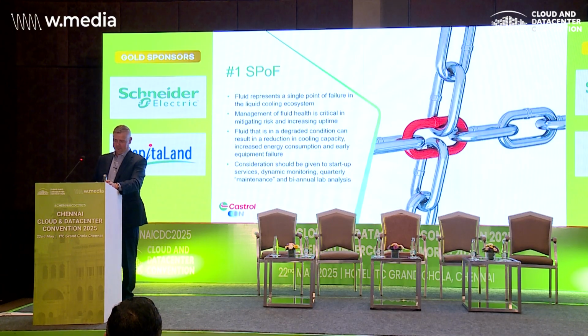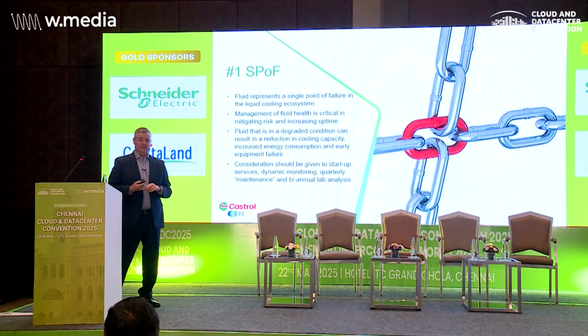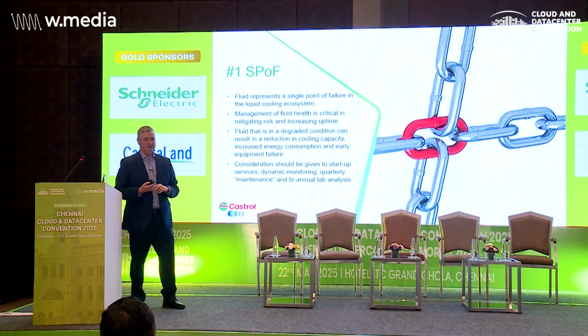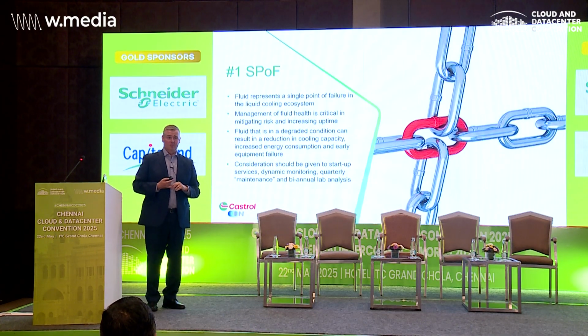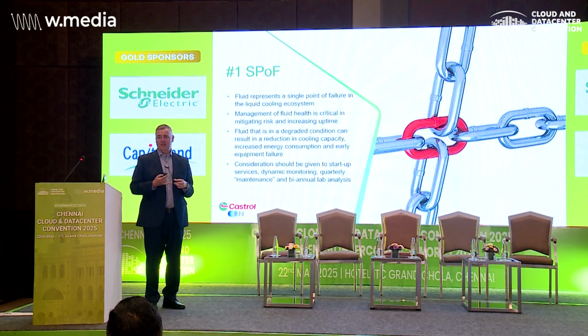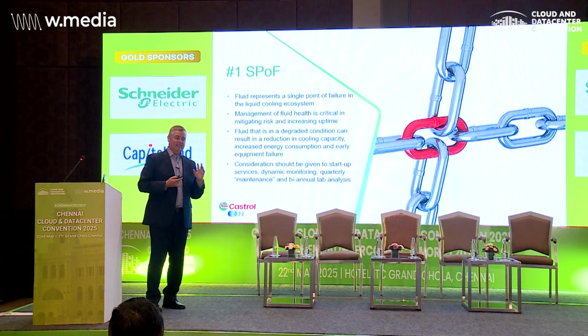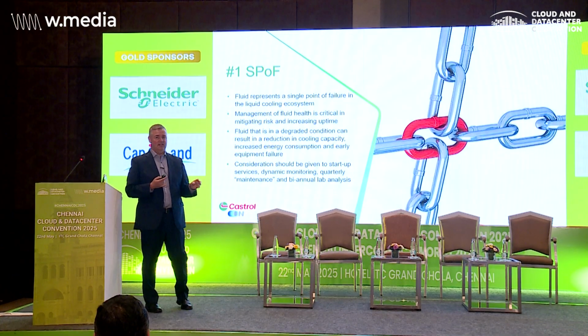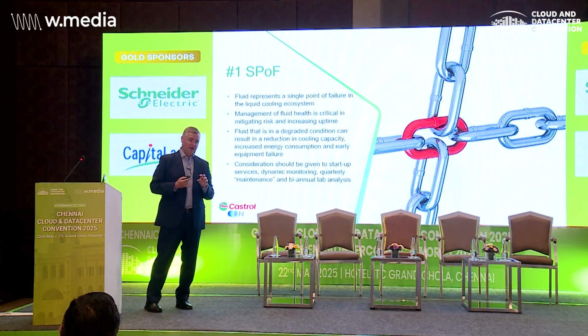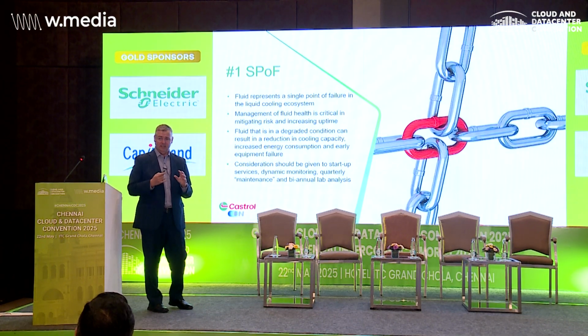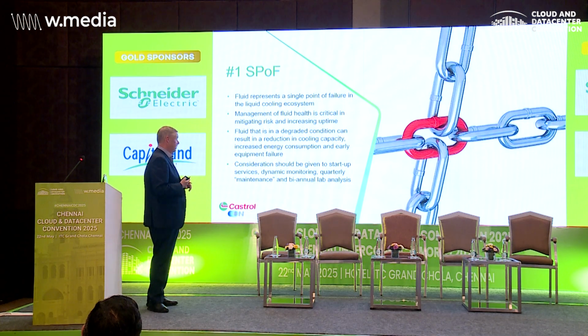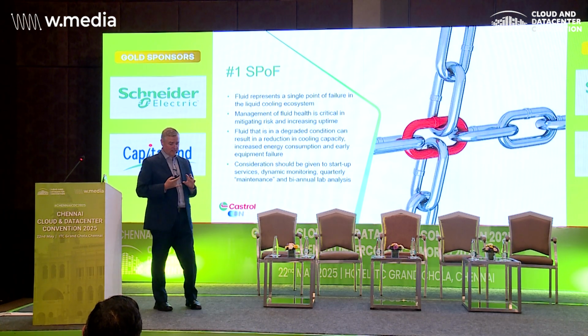First thing you need to know: you've just introduced a single point of failure into your data center. We build up all this redundancy in power and cooling infrastructure, and remember when I said I put it in the middle? That's because there's only one fluid. So the health of that fluid is absolutely critical. This is not a fill it and forget scenario. You need to understand it, you need to maintain it. So managing that is critical.